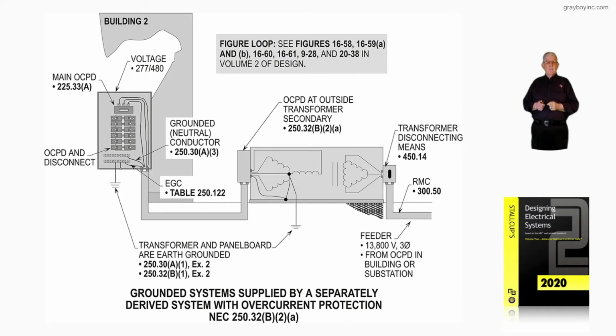Now, this illustration deals with grounded systems supplied by a separately derived system with overcurrent protection ahead of the conductors on the primary, basically speaking. In accordance with NEC 250.32(B)(2)(a), as in boy, 2A as in apple. Now, before we get into this transformer located outside supplying the building, let's look at the figure loop.